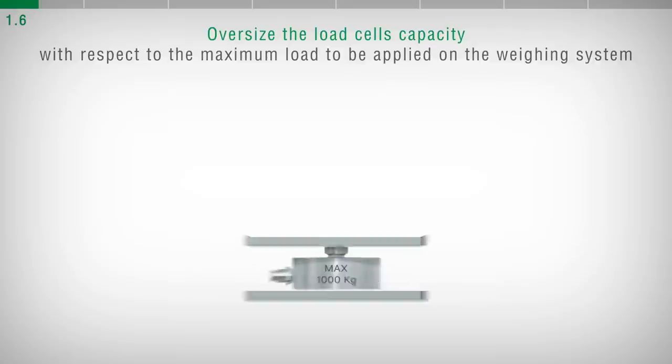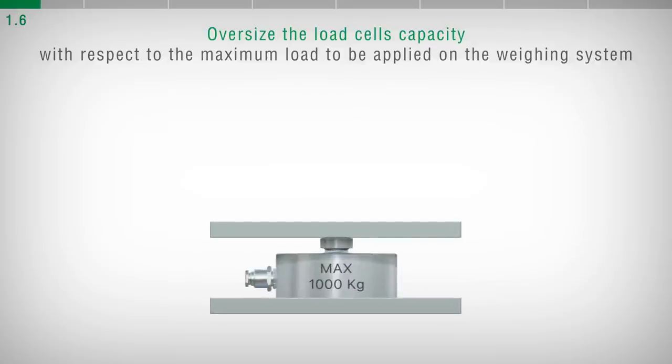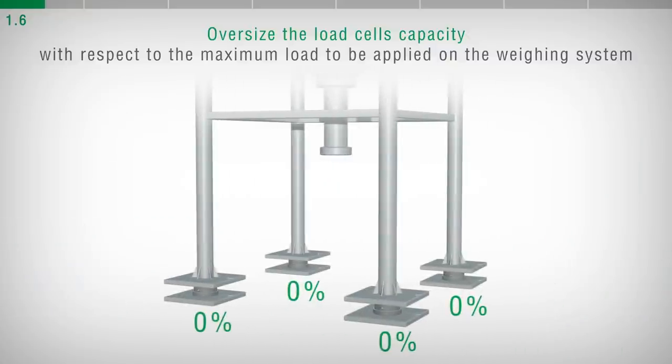For safety reasons, it is recommended to use the load cells at a maximum of 70-80% of their nominal capacity. In case of weighing structures with four supports, consider that the load will not be uniformly distributed and that 85-90% of the applied load will be distributed on just three supports.